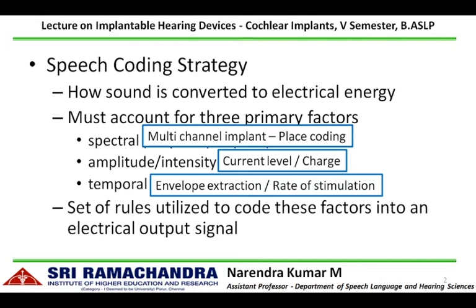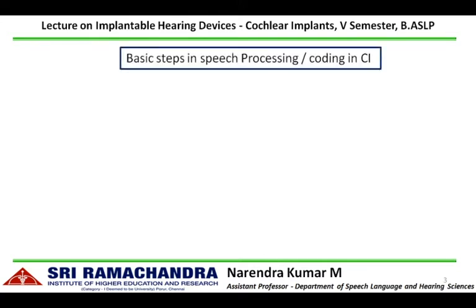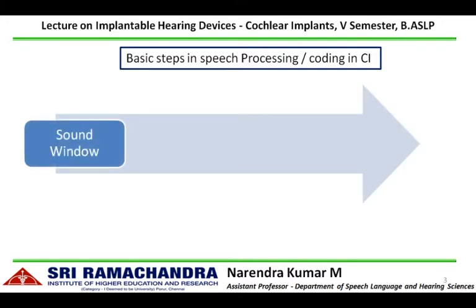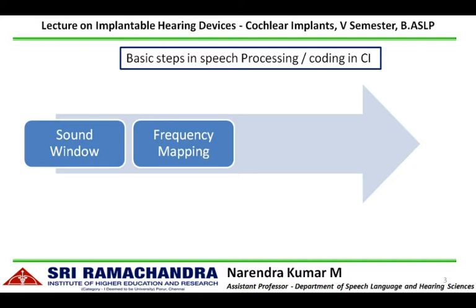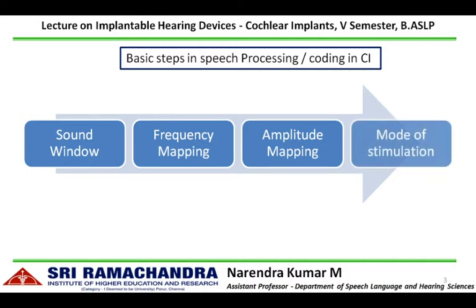The basic steps involved in speech processing in a cochlear implant start with a sound window, which determines what sounds need to be picked up and processed. Once selected, the sound window is subjected to frequency mapping, where the sound is split into different frequency components, followed by amplitude mapping — how the signal is represented in terms of its amplitude. Then the mode of stimulation determines how the processed information is delivered at the intracochlear electrode array to stimulate the auditory nerve fibers.